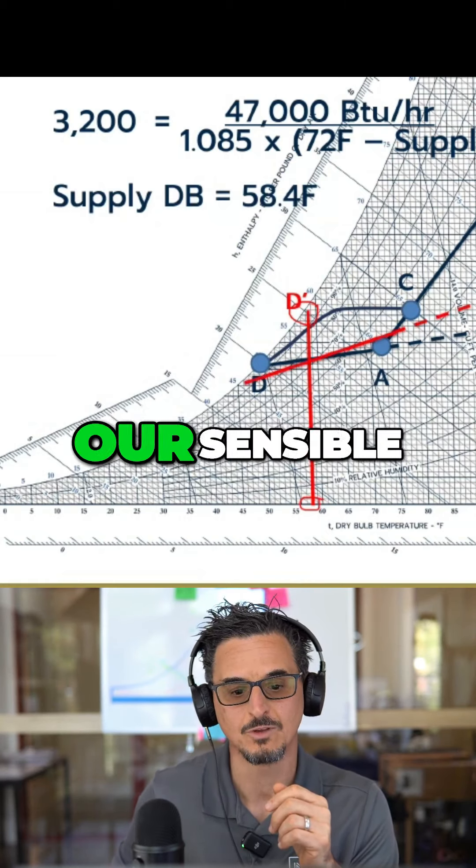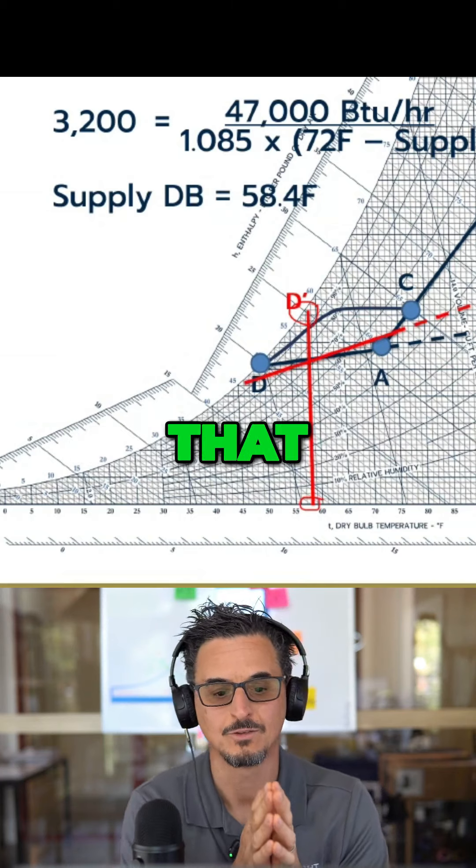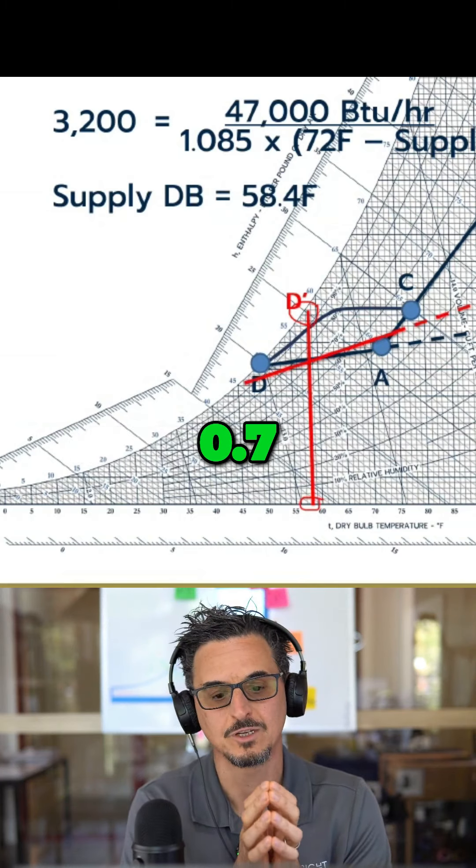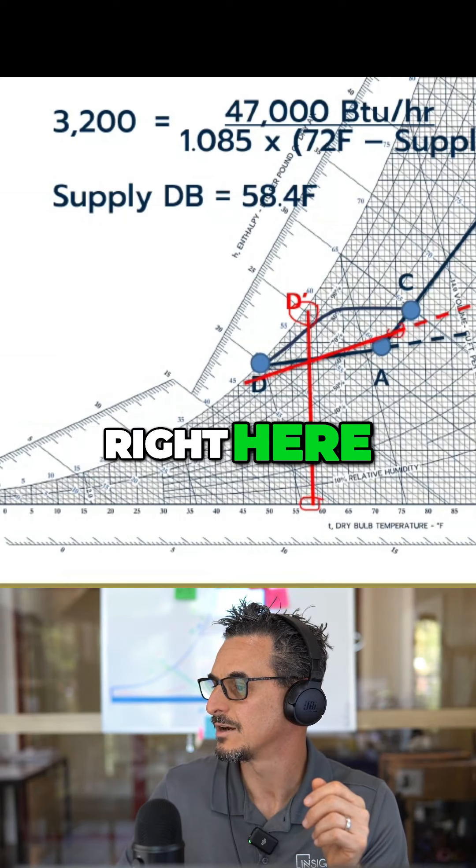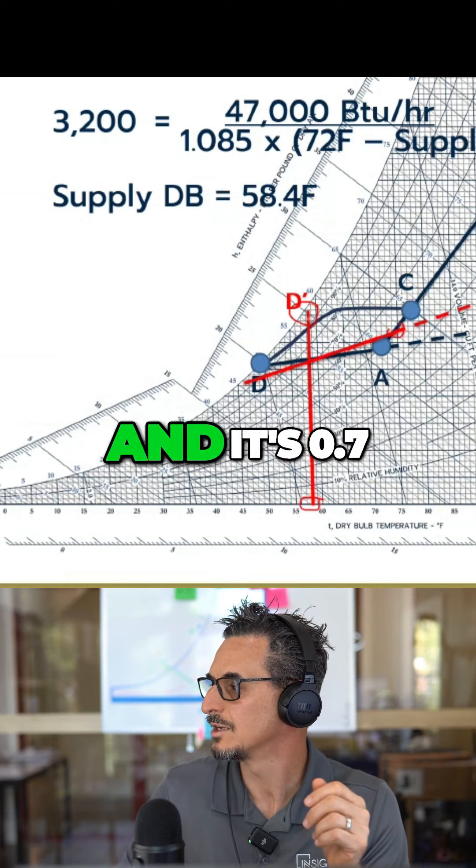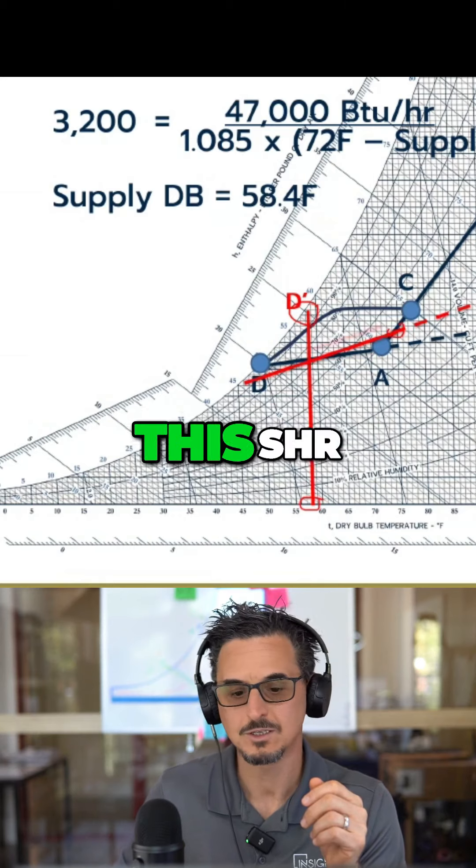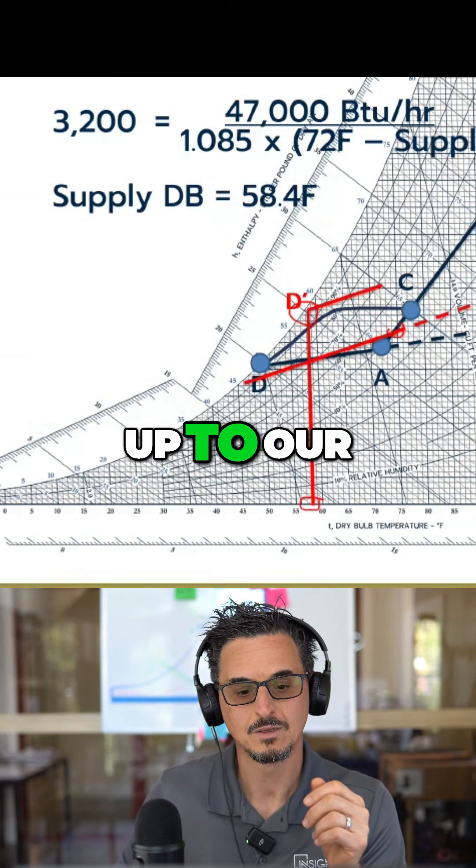So we use our sensible heat ratio to determine that. If we draw the SHR of 0.7 again, I'm drawing it through the index point which is right here, just to get the slope, and it's 0.7 here. Now we move this SHR up to our condition here.